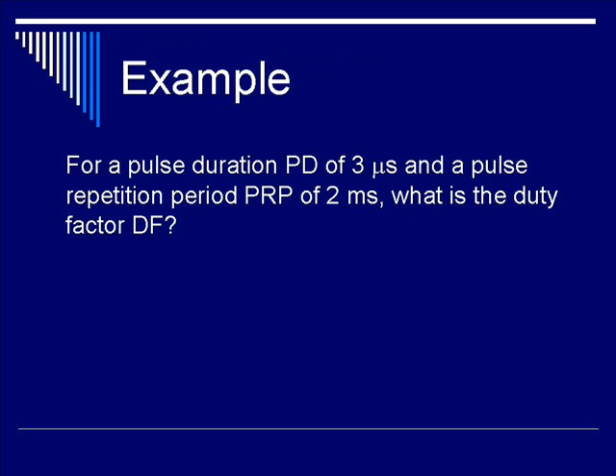Let's do an example. For a pulse duration PD of 3 microseconds and a pulse repetition period PRP of 2 milliseconds, calculate the duty factor DF. Recall the equation shown earlier. Utilize PD of 3 microseconds, which can be rewritten as 0.003 milliseconds.